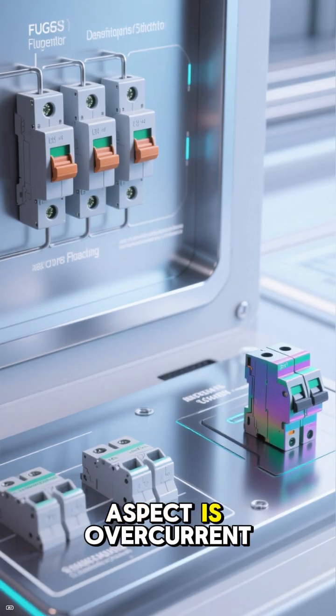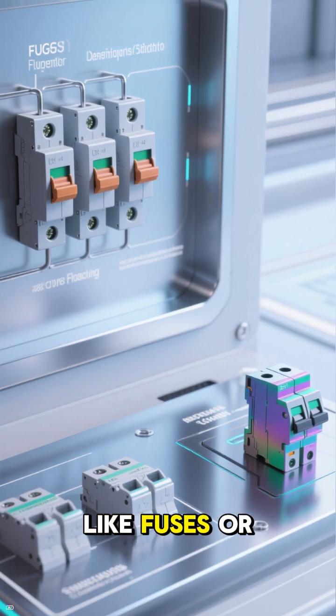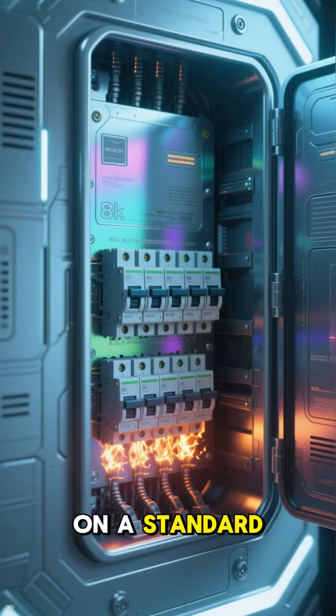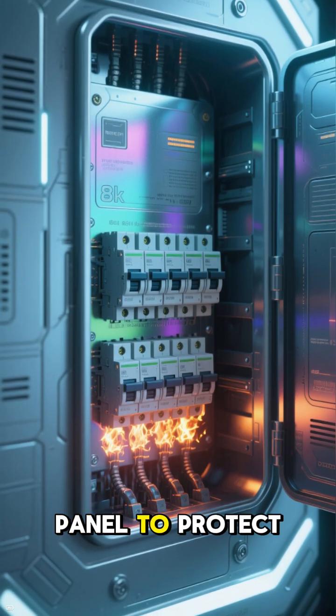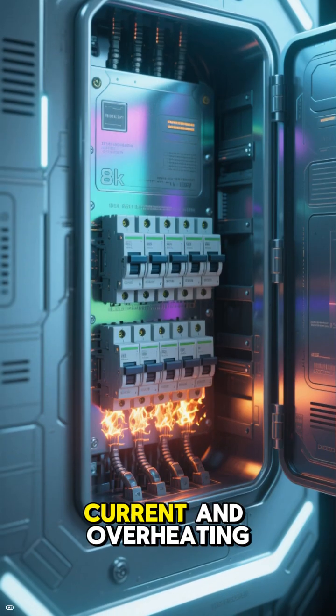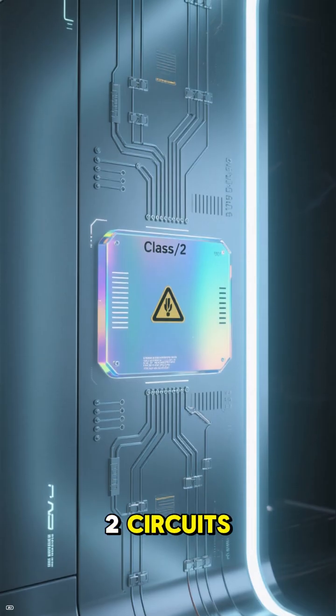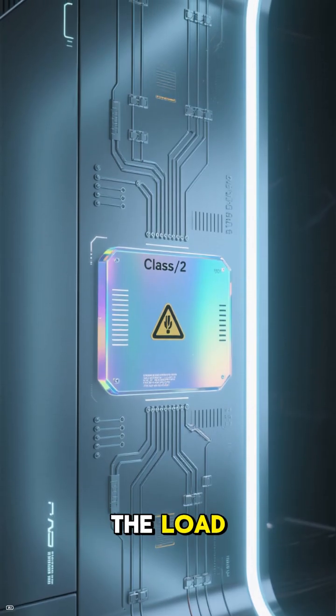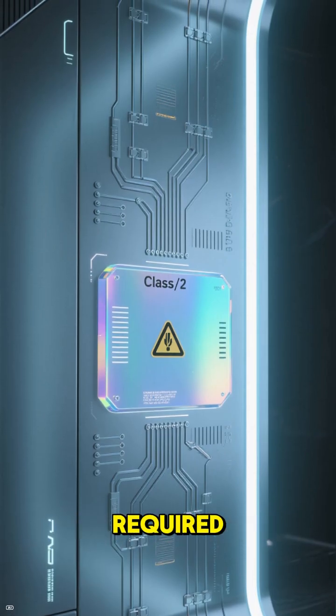Another interesting aspect is overcurrent protection, like fuses or circuit breakers. On a standard circuit, you have a breaker in your panel to protect the wires from drawing too much current and overheating. But for Class 2 circuits, overcurrent protection on the load side of the power supply is not typically required.